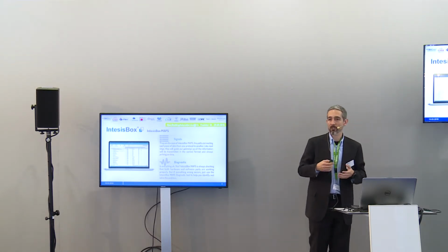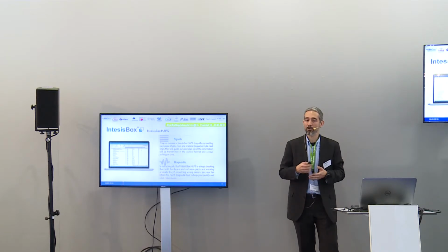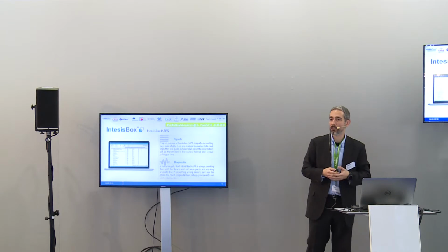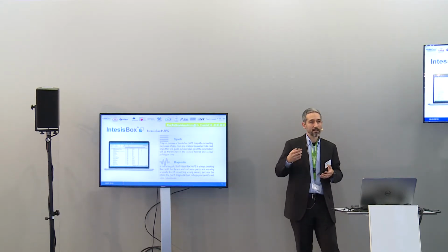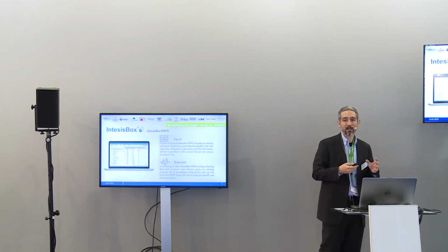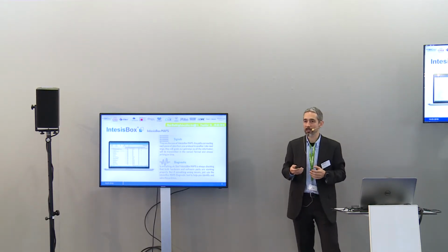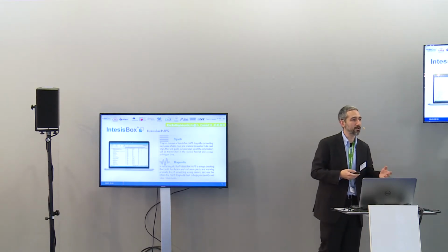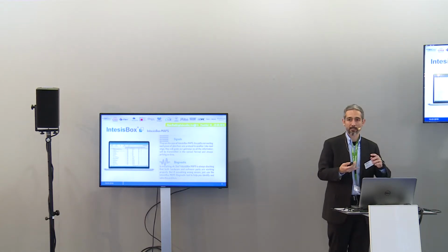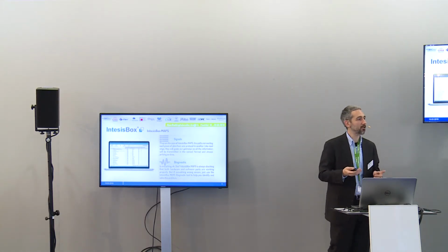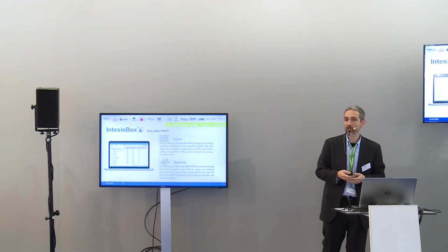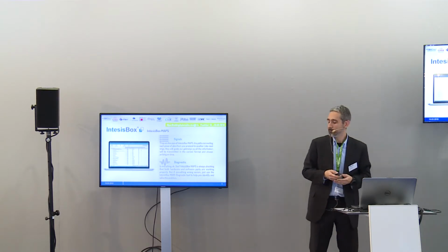Apart from that, we have a special feature where you can directly push a single button and the box is set automatically into diagnosis mode. This will start logging information for the different buses and store this information in a zip file that can then be sent to our support team. This helps a lot to improve the time of solving possible issues, as our team has all the data in advance: logs for the communication in both protocols, information about the box itself, the current firmware, and any other relevant information that our support team requires.